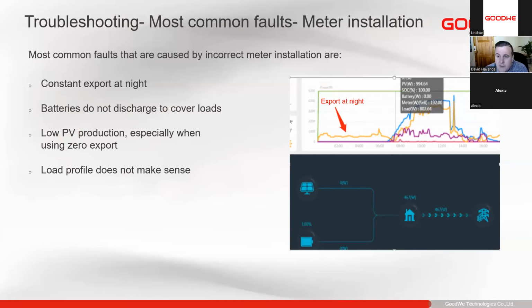Also, if you're using zero export, you'll have very low PV production, as you'll see in this example. And the load profile does not make any sense. As you'll see, at night our load is 0 because it's being negated by the meter readings.